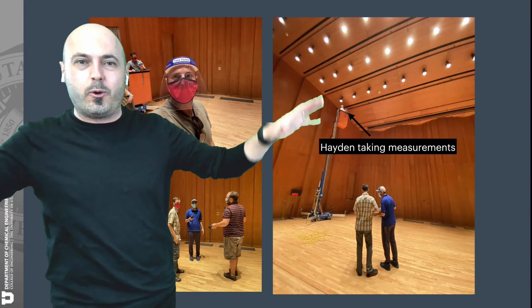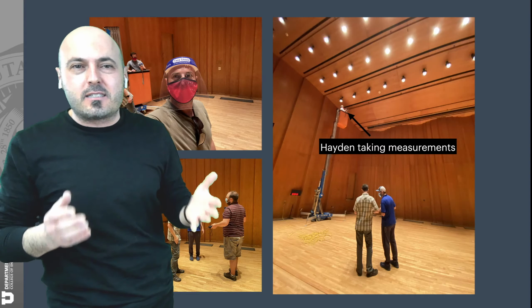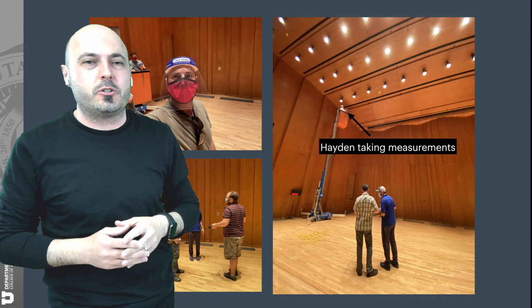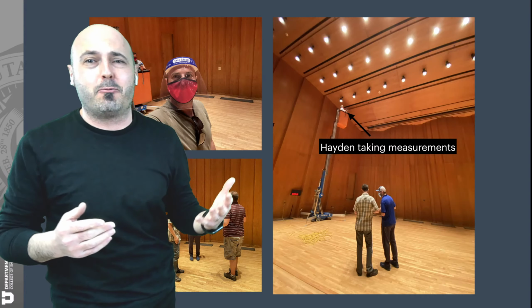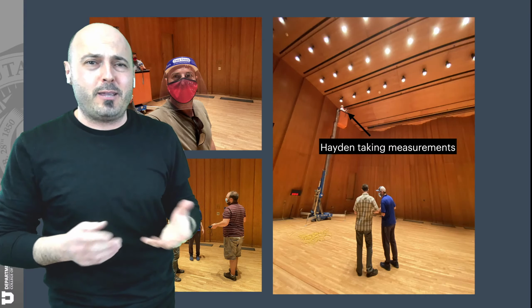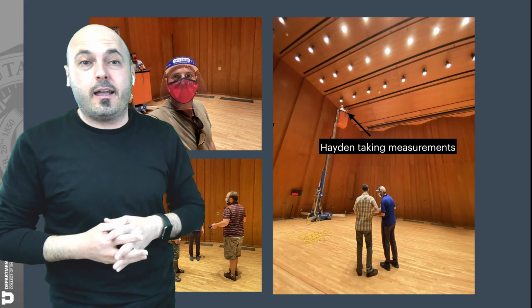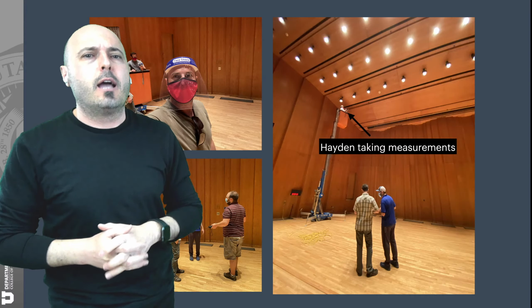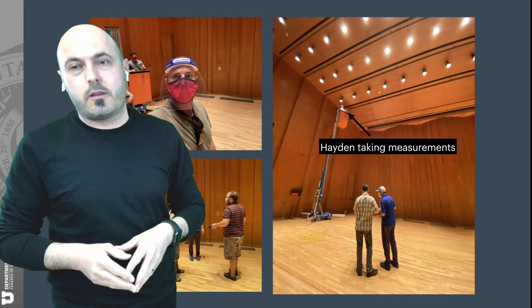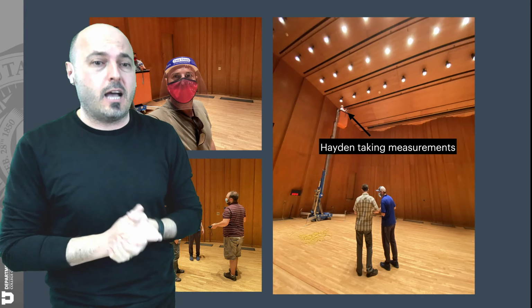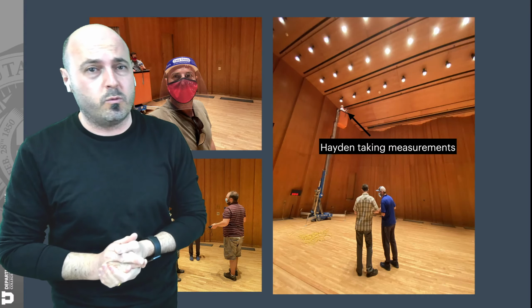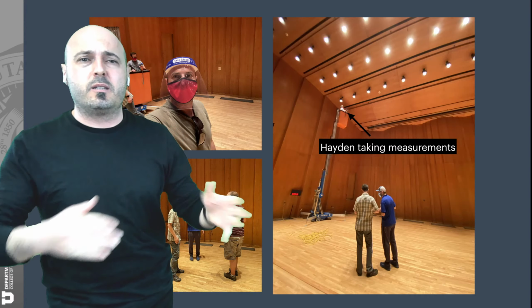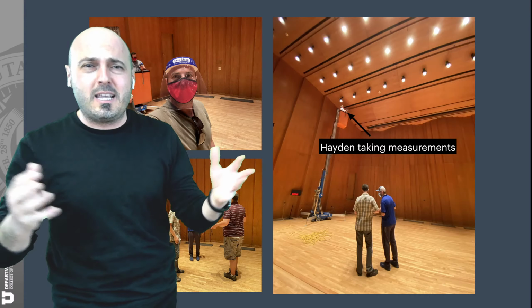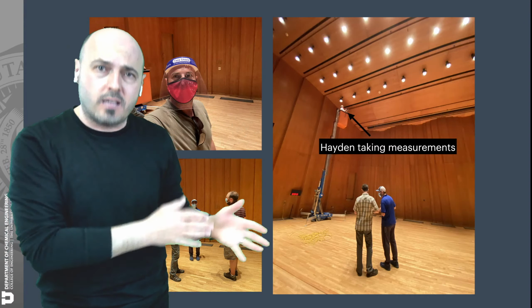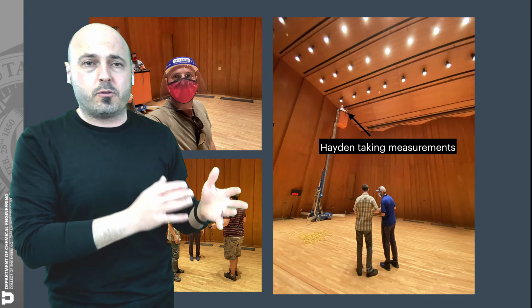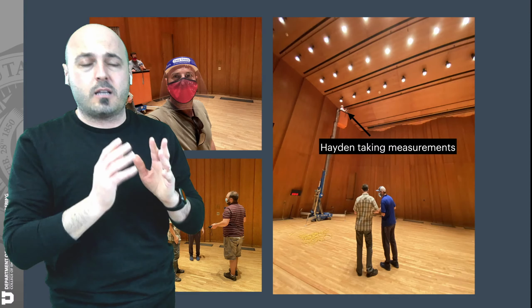We wanted also some data points across the hall to get some sense of verification later after we finish the simulations. Their velocities were just zeros everywhere. There was one cell that had 0.1. We emailed them saying that doesn't make sense at all, and one of the people responded that it has to do with turbulence. So we rolled up our sleeves, got down ourselves and did the measurements ourselves. Velocities were not 0. We took several measurements and took an average just to get a sense of where we're at. We compared that with the design numbers provided to us by Salt Lake County, and we were very close to those design numbers.